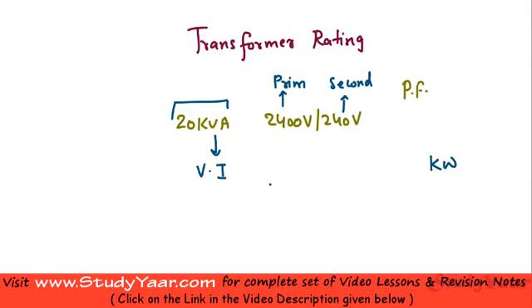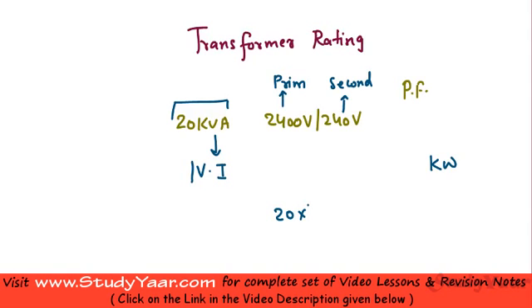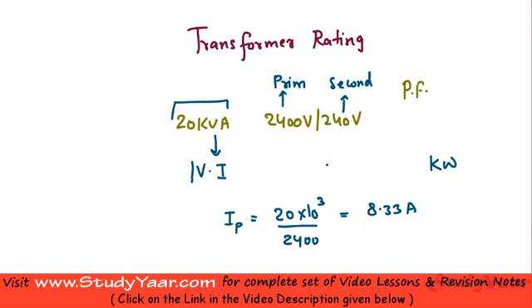Based on this value, you can also find out your maximum current. These are also known as your rated values — rated power, rated voltage in primary, and rated voltage in secondary. Since 20 kVA is the product of voltage and current, and your voltage in primary is 2400, your current in primary is 20 × 10³ divided by 2400, which comes out to be around 8.33 amperes. This is known as your rated current.